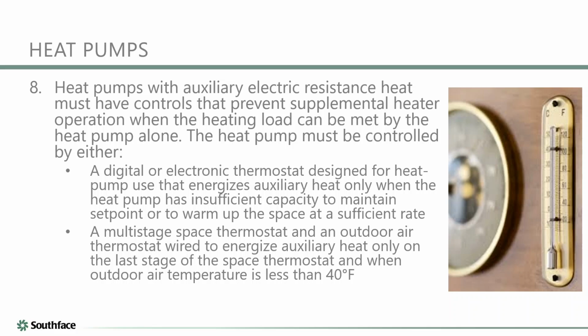The point is really just to rely on the heat pump, know that it's designed to reach a certain set point, and then it can do that. I think we're just too quick to jump on that emergency heat sometimes. So taking that control out of the occupant's or the building owner's hands and just locking that into, say, an outdoor thermostat that's set at 48 degrees, I think that's just going to be a little bit better.